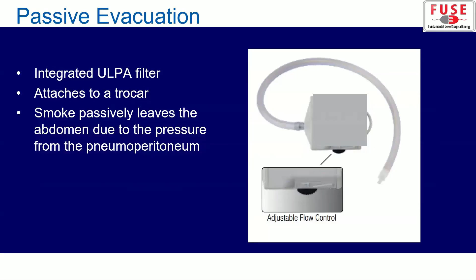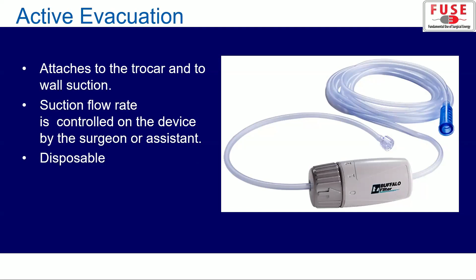And then I think this is more common, and I've seen more, as active evacuation, where you attach to the trocar on one end and you attach to suction on the other end. So this is active evacuation, and it suctions. You can adjust the flow rate, the suction rate, also to strong or weak, and this filters the surgical smoke within the abdomen through a ULPA filter as well. These are disposable. Next slide, please.